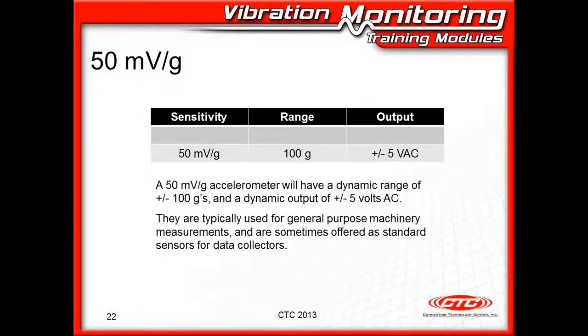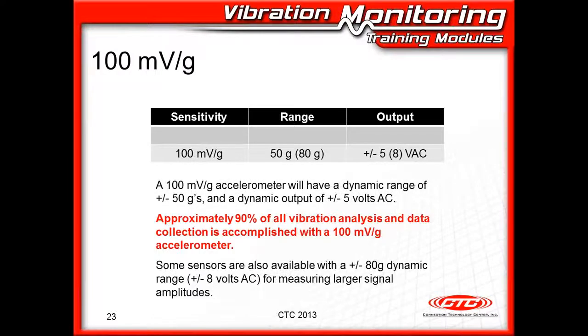The 50 millivolt per G sensor is well liked by Entek Rockwell. They seem to have settled on this as their general purpose sensor, and I believe that is due to the 100 Gs of dynamic range. It still has a nice sensitivity and a little bit more dynamic range. It allows them then to have a little broader application possibly. Still though, 50 millivolts per G times 100 Gs is plus or minus 5 volts AC. So again, you'll have a maximum output of plus or minus 5 volts AC.